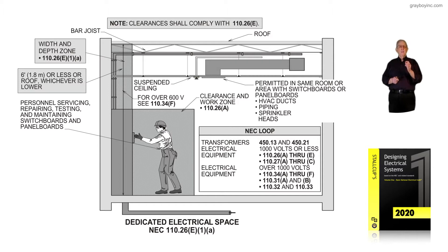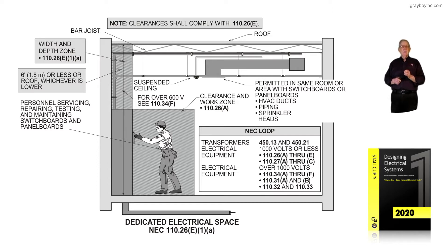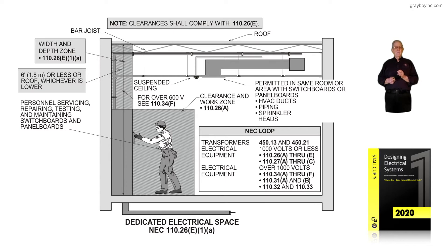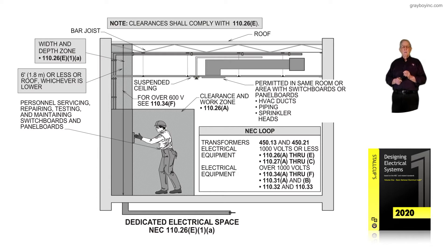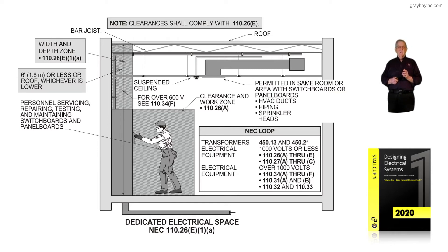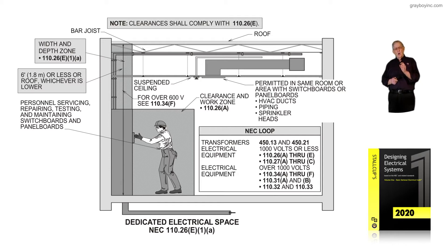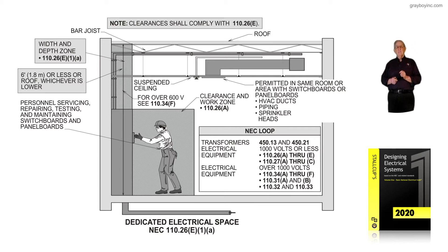Notice the width and depth zone is 110.26 E as in Ed, one little A, and then notice the six-foot rule or less above the electrical equipment is shown, and notice that six-foot goes all the way up to the roof level with a suspended ceiling installed between that six-foot, which is legal by code, and notice that it's over 600 volts in 110.34F if we use OSHA regulations.